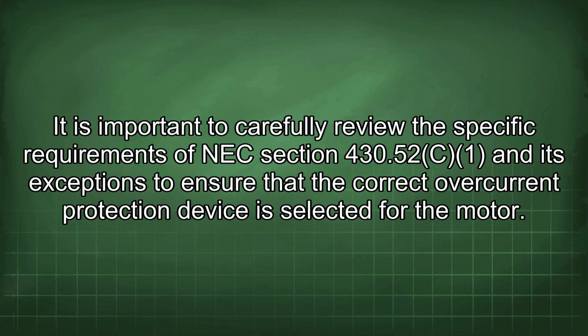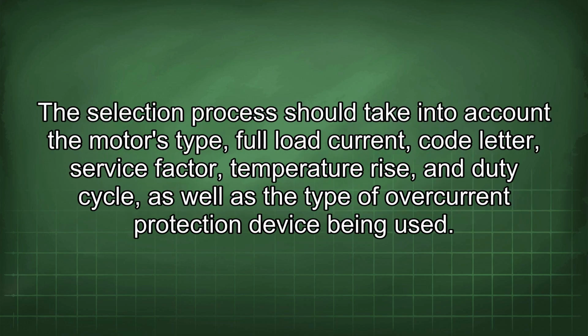It is important to carefully review the specific requirements of NEC Section 430.52 and its exceptions to ensure that the correct overcurrent protection device is selected for the motor. The selection process should take into account the motor's type, full load current, code letter, service factor, temperature rise, and duty cycle, as well as the type of overcurrent protection device being used.